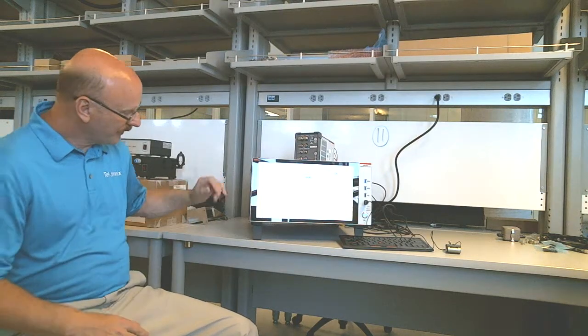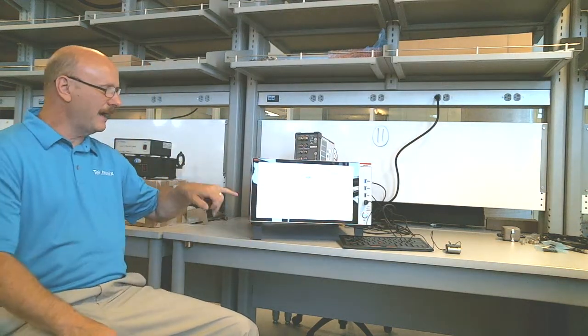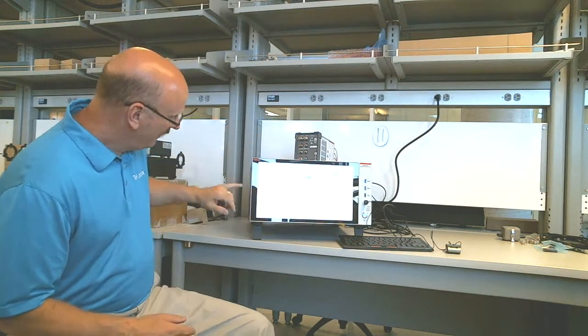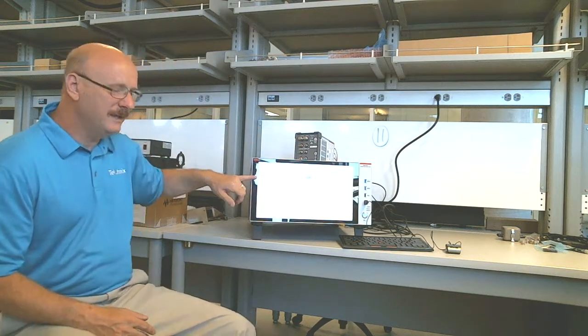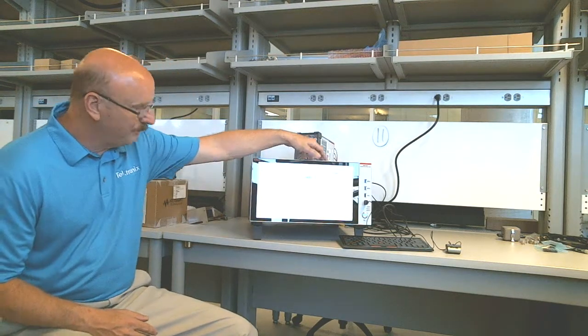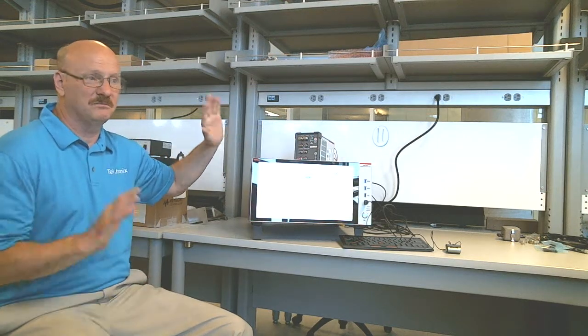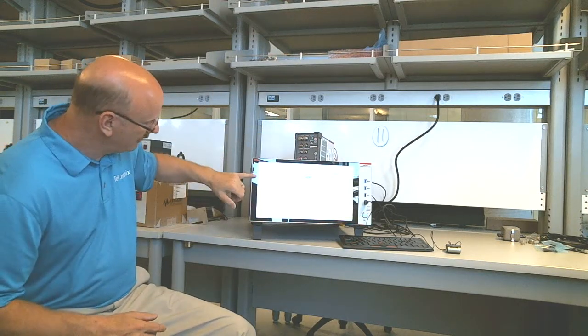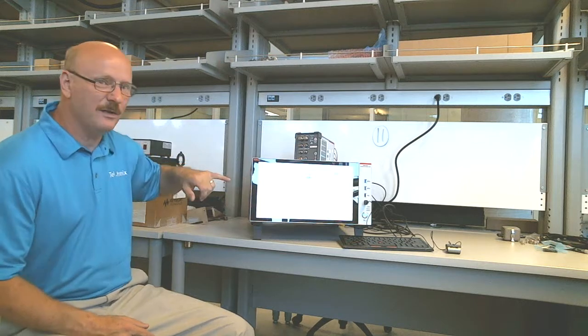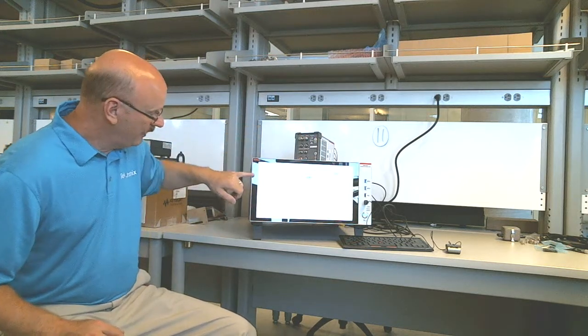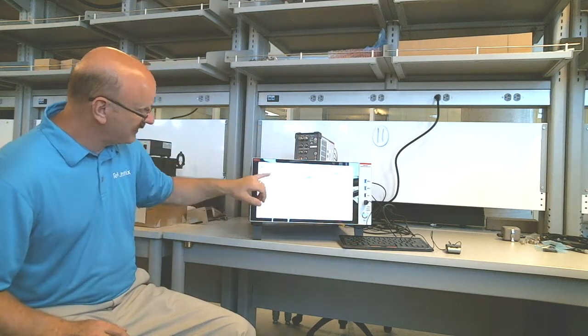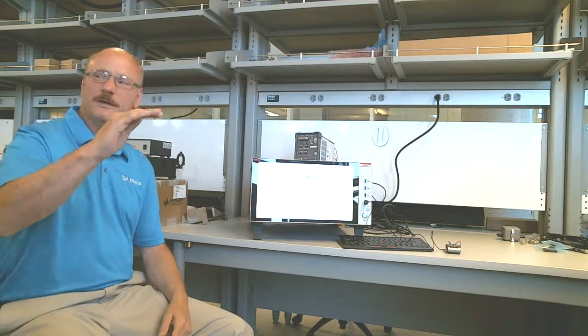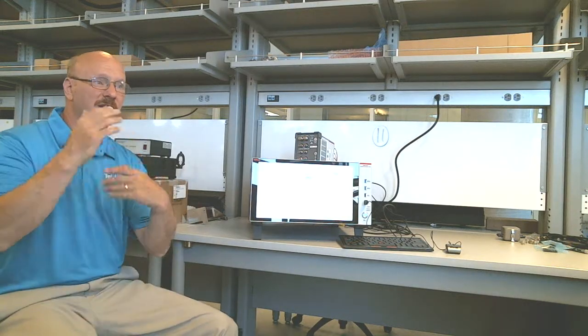You see the check boxes down the side. So what that means is, if I select this VDS ID that's selected now and hit the run button, it'll run that test only. But if I go up one spot to the device itself and hit run, it's going to run everything within that device that's got a checkbox, one after another. So you can sequence things together.